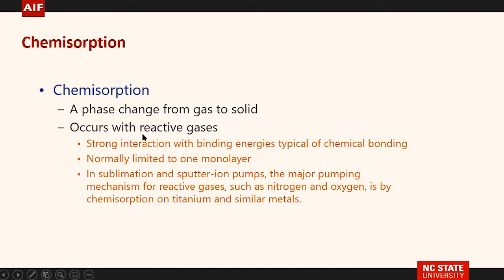Another term is chemisorption. Here we're going from a gas to a solid. This occurs with reactive gases, and you'll see this in some of the pumps where we use titanium, and fresh titanium likes to absorb and hold on to materials such as hydrogen, oxygen, carbon, etc.